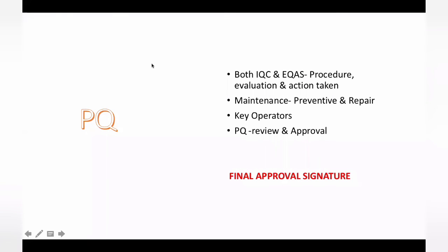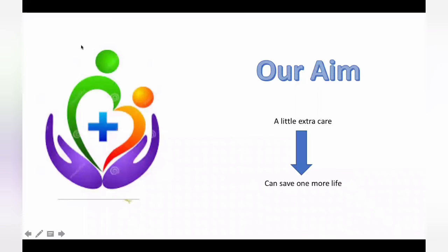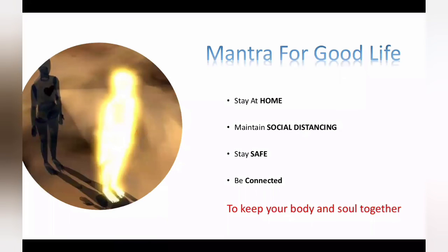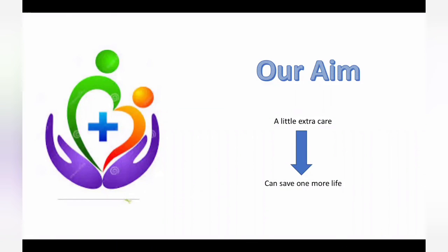Maintain your records in this way: pre-installation, installation qualification, operation qualification, performance qualification. And remember one thing, whatever they have mentioned in 5.3.1.7, you are not missing any part of that. See, what is our intention ultimately? Whether this is the understanding of measurement uncertainty, or risk management, or lot acceptance testing, or this IQ, OQ, PQ, we want to make our results error-free. Our aim is, with a little extra care in our laboratory, we can save one more life. This is our intention.